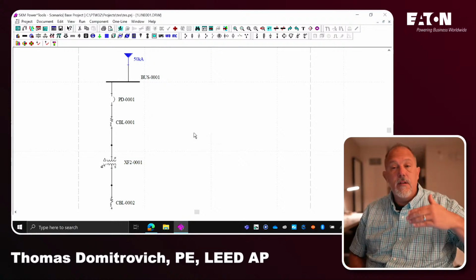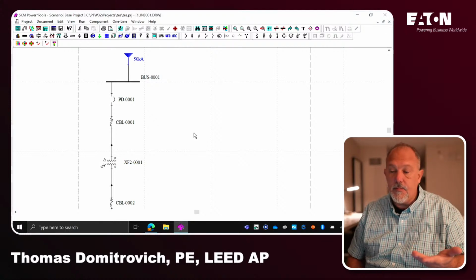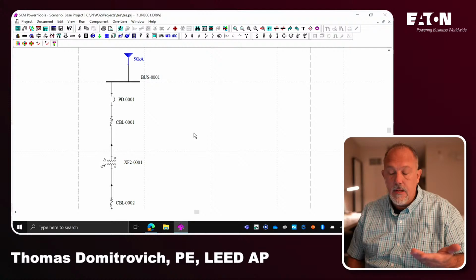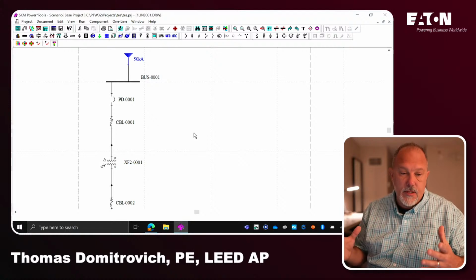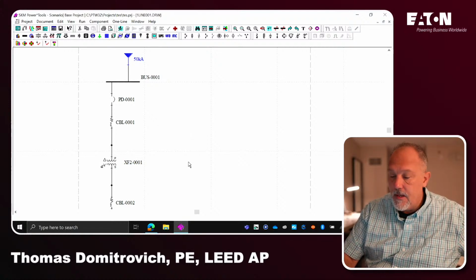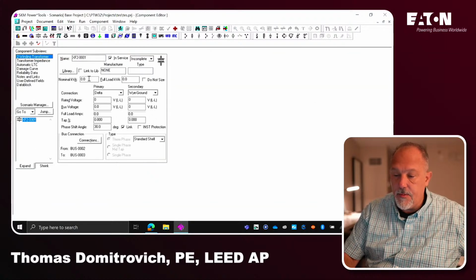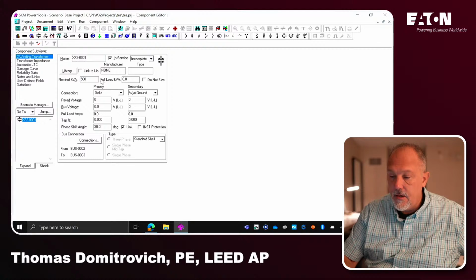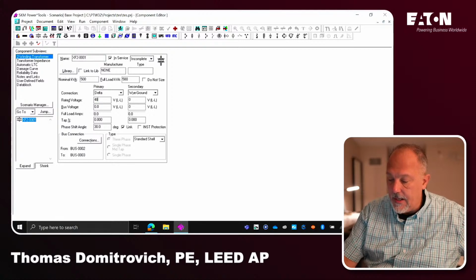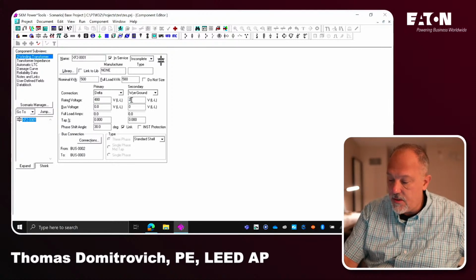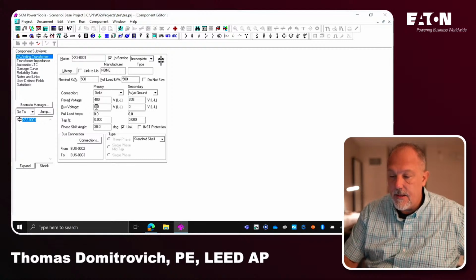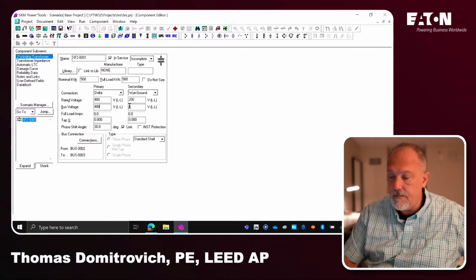50 kA. Now I'm using a utility configuration, but what I'm doing is simply providing a fault current source, whether that be a utility, whatever it is. So I have an X to R ratio, that's all I need, right? All right. So then I come down, and I'm going to put the transformer data in. I'm going to put a nominal kVA of 500. Full load kVA is 500. Primary voltage we said was 480. Secondary voltage we said was 208. And the bus voltage will be 480. And the line-to-line bus voltage will be 208.